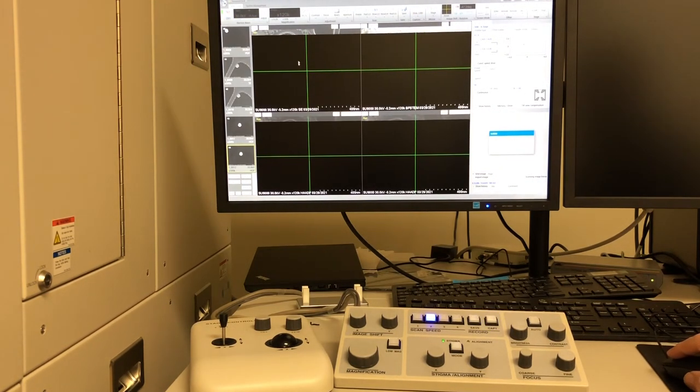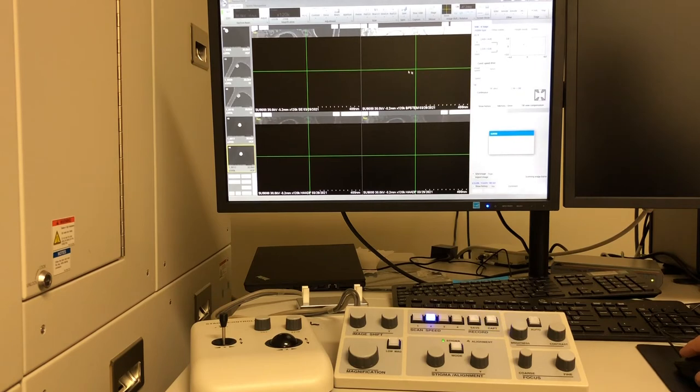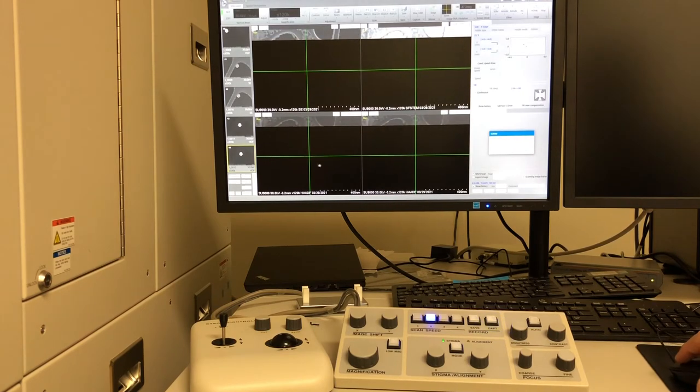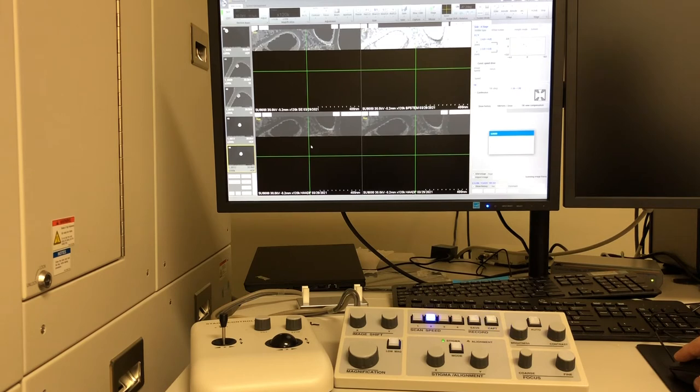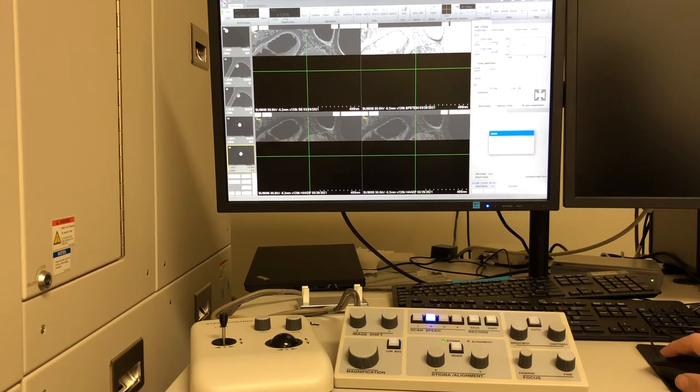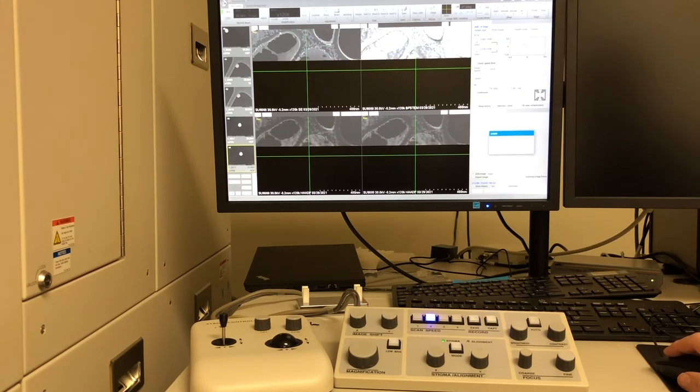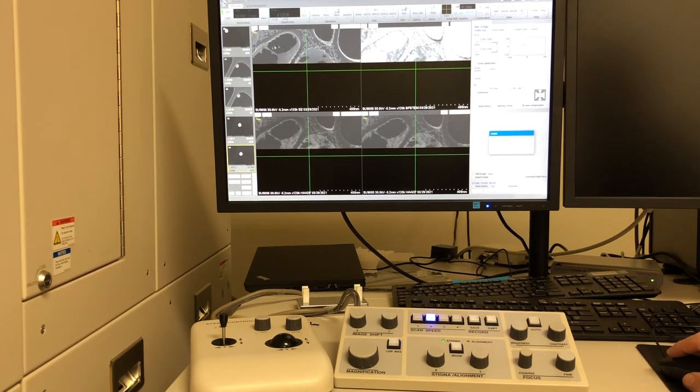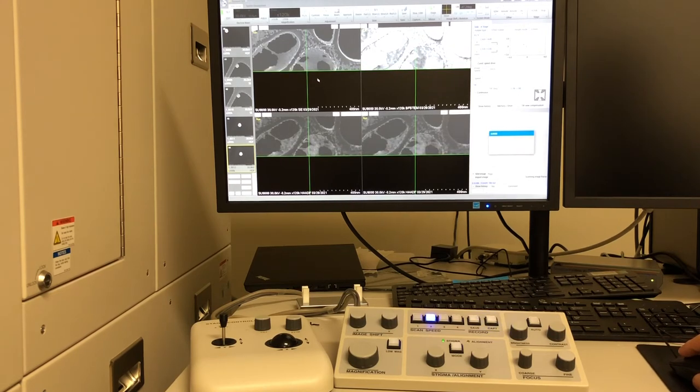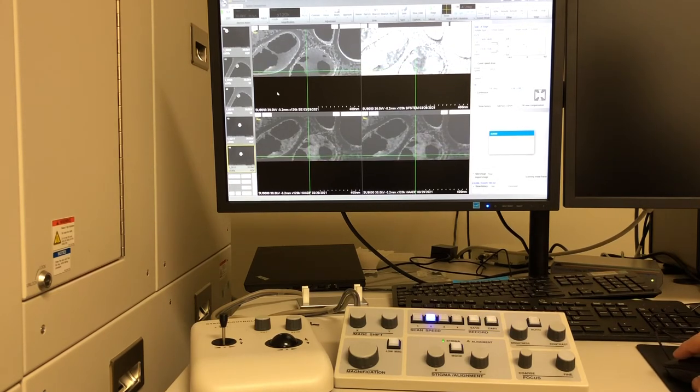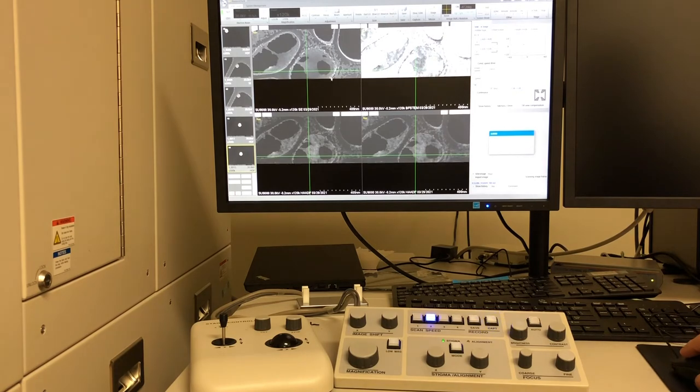Now we can save them by pressing the slow 1280 button, and that will simultaneously save our SE image, our bright field, and our HAADF. It's doing so by slowing the beam's raster down over the sample as well as integrating the image for us to give a very crisp image.